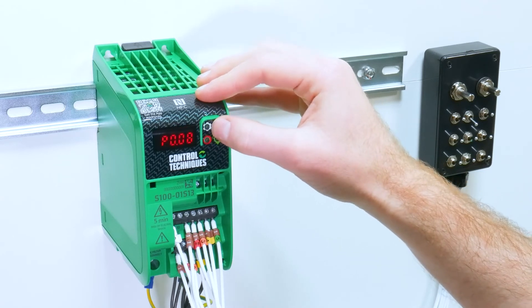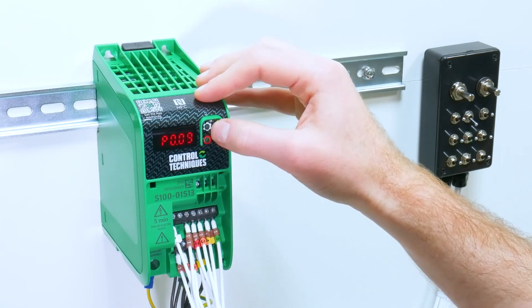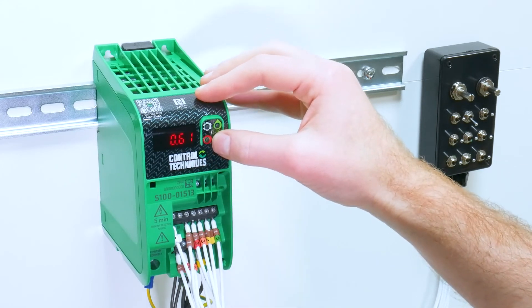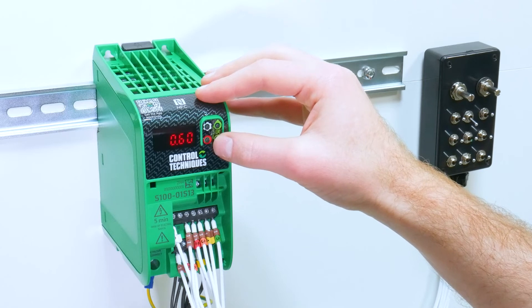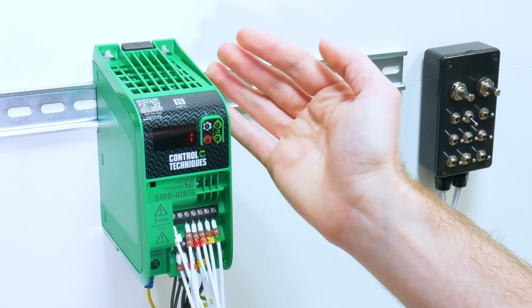Parameter eight is our motor rated voltage. Parameter nine is our motor rated power factor. Parameter ten is our run stop configuration, and a setting of one means enable run forward and reverse.